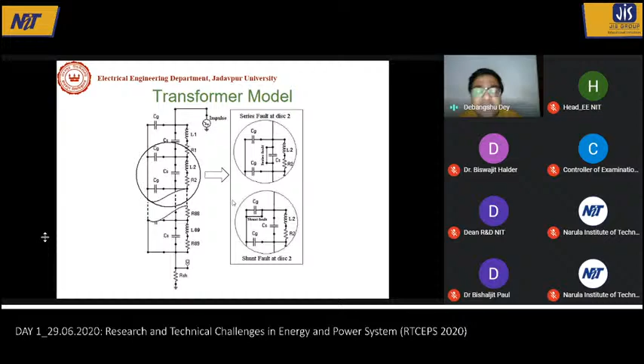So if some fault occurs, there will be some change in the response. That fault can be of two types, either series or shunt. Shunt means that CG will not be present, and series means that CS will not be present, because turn to turn shorting of the winding will occur, and for shunt there will be some shorting of the winding to ground. So these are the two typical types of faults that usually occur in a transformer winding, and the response curves look like this. You can see A and B just show the series fault at different disks, different locations. And you can see the two waveforms are very similar to each other. Their nature is very similar. They are different. We can distinguish them by naked eye, but it is very difficult to set one rule base for them.